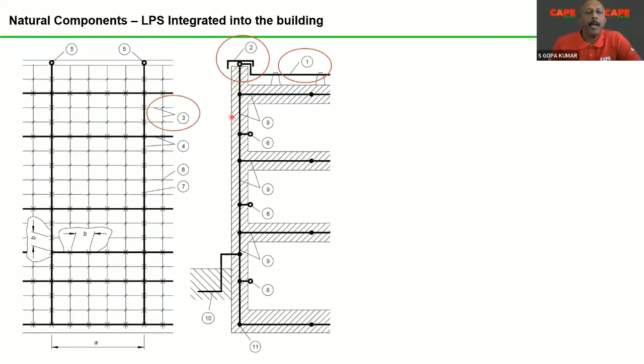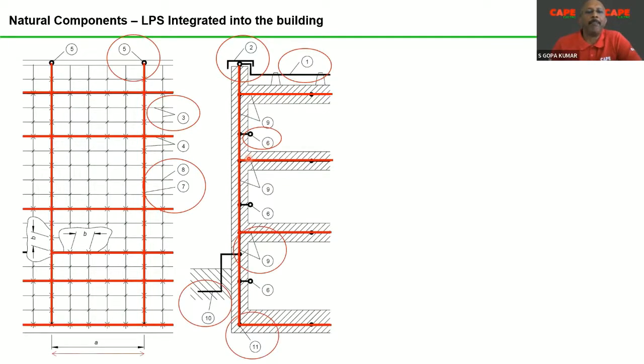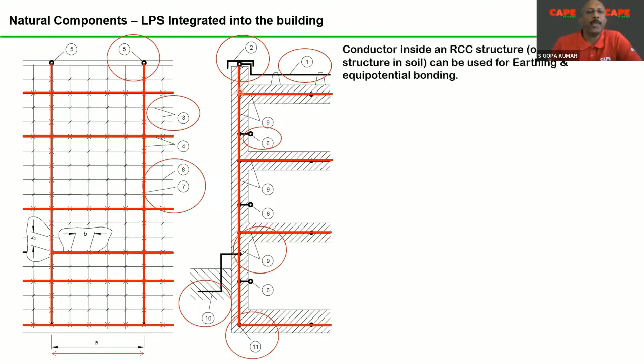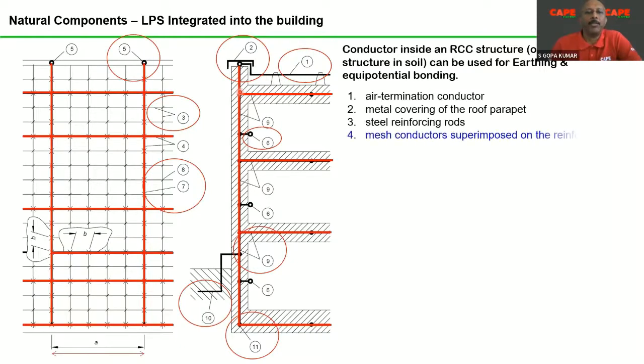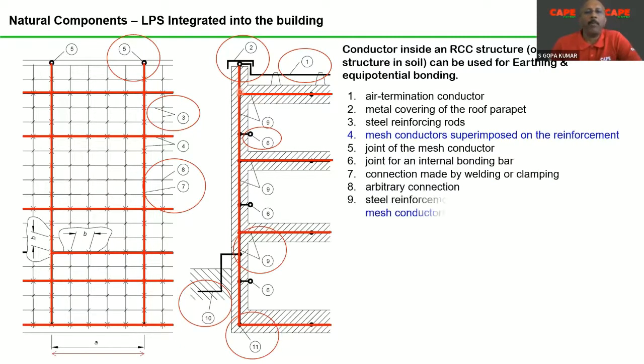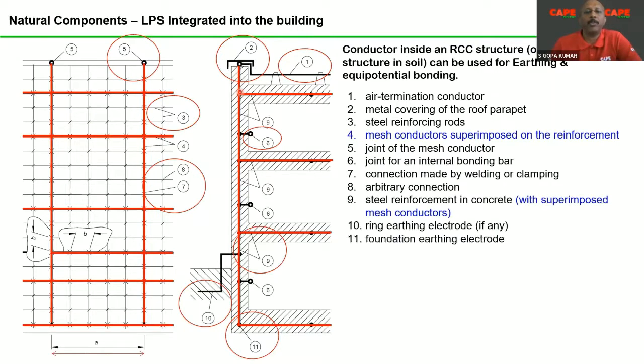Then the black line, which I have changed to red, means an additional conductor embedded inside the concrete. Now you have item number 6, which is basically some kind of equipotential bonding connection. Please understand that this is a typical picture. Each of these components has to satisfy its requirements. There are several technical requirements. It is not like you put a conductor from top to bottom of the building and your job is done. It is not like that.